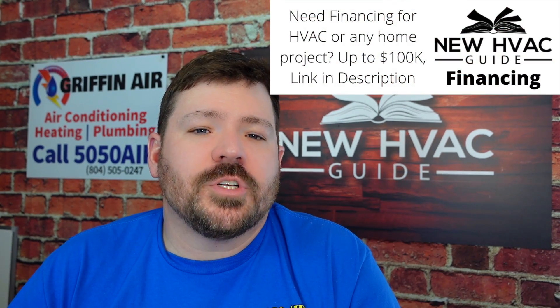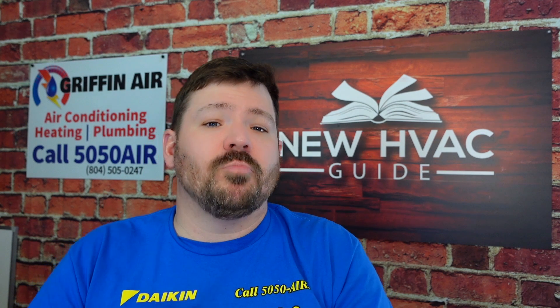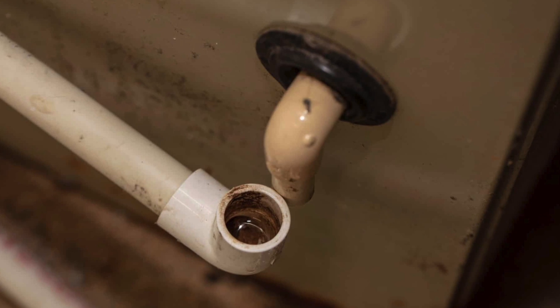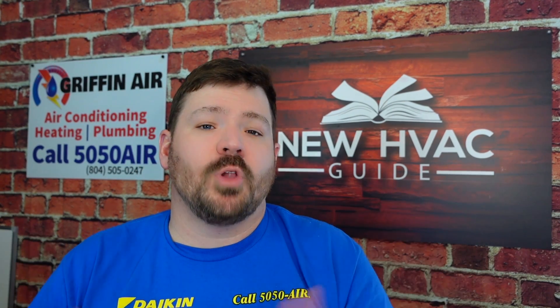The guy that I learned under was starkly against it. Years ago I went to a job site where a technician had blown the drain out and the customer had water coming through their ceiling. What happens is when you're blowing compressed air through that drain, if the drain itself was not glued properly, primed properly before being glued, or just simply not installed right, it's possible to actually blow holes into that drain — whether the pressure causes the drain to spring a leak, or fittings that weren't glued or primed properly separate, creating issues.